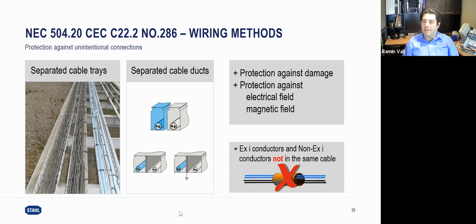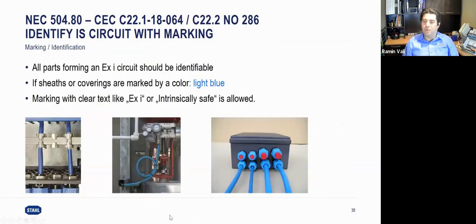And finally, the NEC 504.80 or Canadian Electrical Code have a recommendation for color, and they mandate us to mark the intrinsically safe signals. So every intrinsically safe signal has to be marked as Ex i or clearly labeled as intrinsically safe, or if you are using a color code for them, it has to be light blue in color. So that's part of the recommendation and mandate imposed by the code.